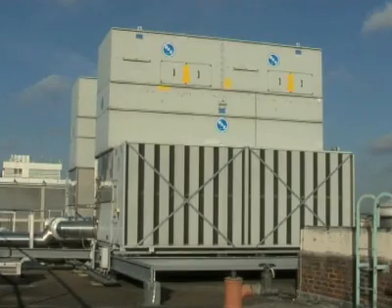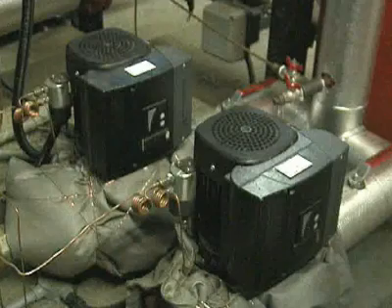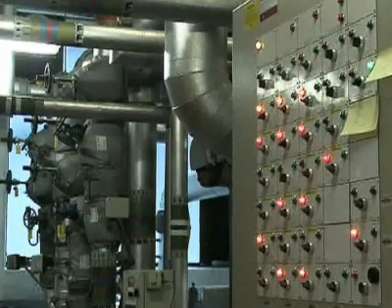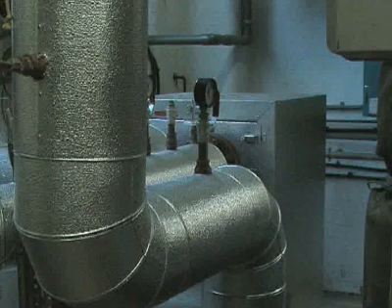The system incorporates plate heat exchangers and pumps in the plant rooms of both museums that keep the hot water flowing. Originally, each plant room had two calorifiers. One of these has been removed and replaced with a plate heat exchanger, and the other calorifier has been retained as a backup.